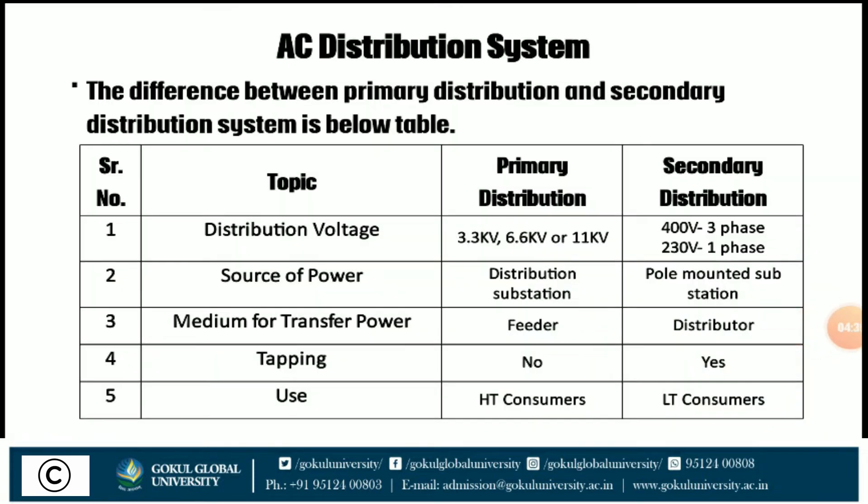Now we discuss about the difference between the primary and secondary distribution system. The first difference is distribution voltage: primary distribution uses 3.3 kV, 6.6 kV, or 11 kV, while secondary distribution uses 400 V for three-phase and 230 V for single-phase. The second difference is the source of power: for primary distribution it is the distribution substation, and for secondary distribution it is the pole-mounted substation.